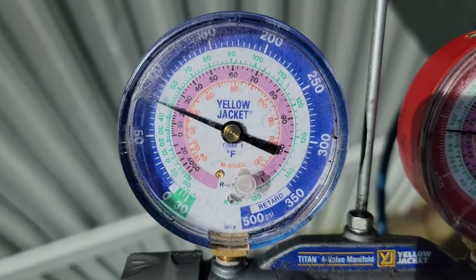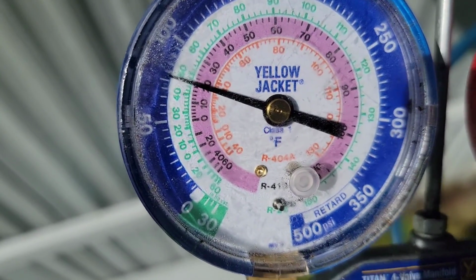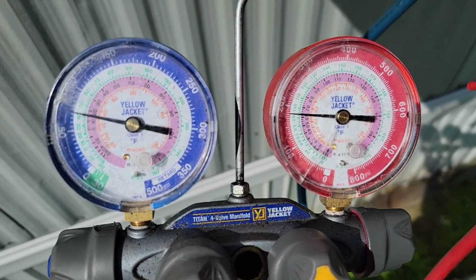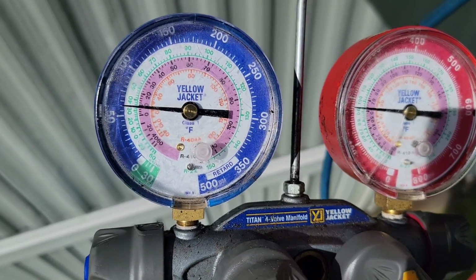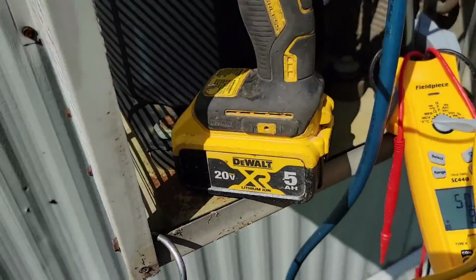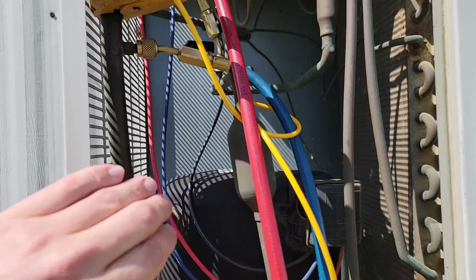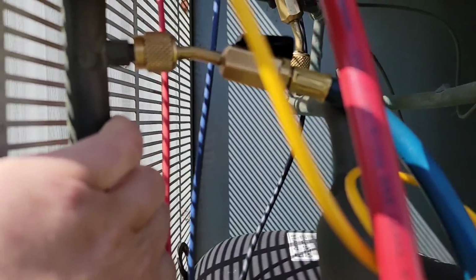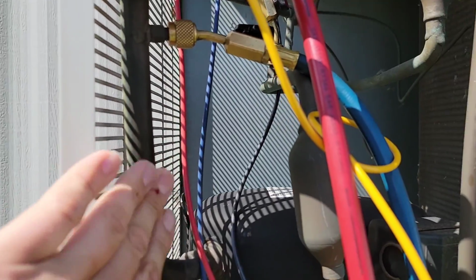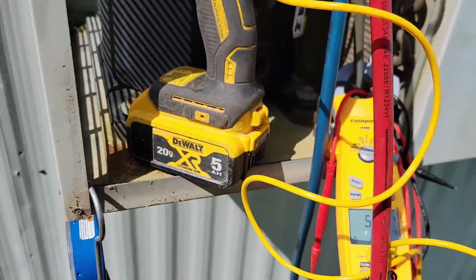So now our suction pressure is up. Let's wait till everything runs for about 10-15 minutes. Then I'll show you the pressures and the temperature. The line is starting to get really cold. Suction line on the compressor starting to get a little sweaty. That's good.